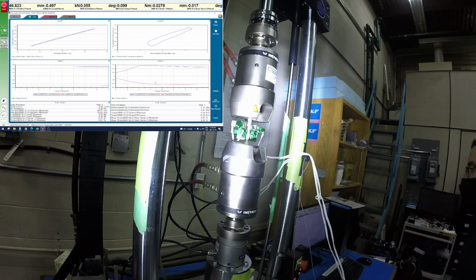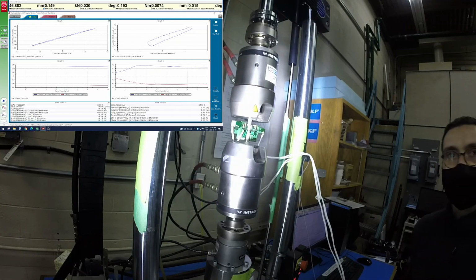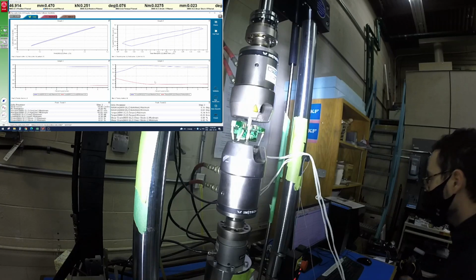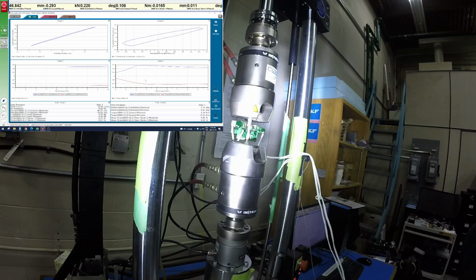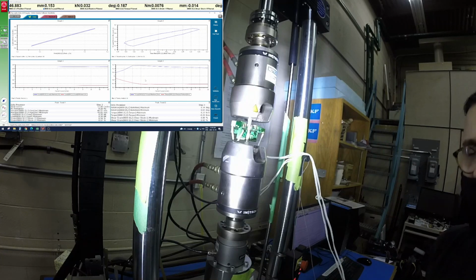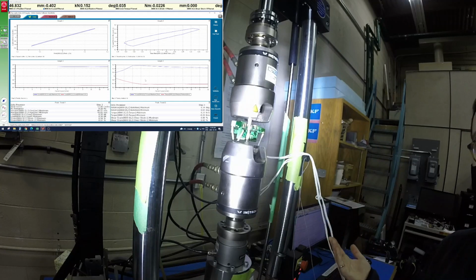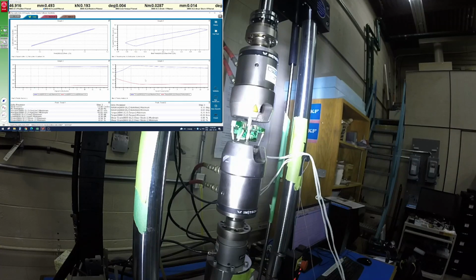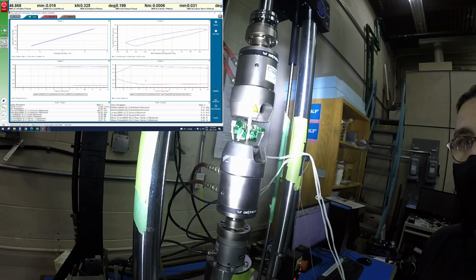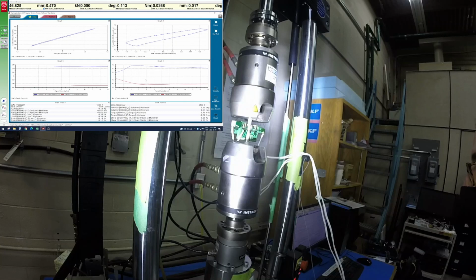and now you can see that the test is running happily. Basically now we monitor the test to ensure our limits are set up correctly. So we want to use the information for the peak and valley here to make sure that the limits are set correctly, and we want to make sure that if we're going to leave the test unattended, all of those are set to a point where it's safe to walk away from the test. And once the test is completed, if we've set our end actions correctly and our specimen protect correctly, we should come back to a failed sample or something that's reached an infinite life, and then we can post-process the data according to the information that we're getting in the CSV file that will be provided by the Wave Matrix software or exported from there.